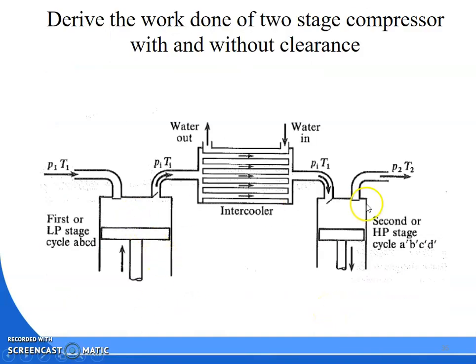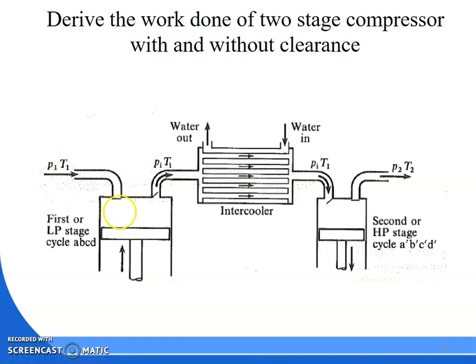You can see here there are two cylinders: one is the low-pressure cylinder and the other is the high-pressure cylinder. The low-pressure cylinder is bigger in size and the high-pressure cylinder is smaller. When air enters at pressure P1 and temperature T1 — that is atmospheric pressure and temperature — the air enters the first stage, which is the low-pressure cylinder. During suction and compression, it reaches intermediate pressure Pi and temperature Ti, and the compressed air is delivered to the intercooler.